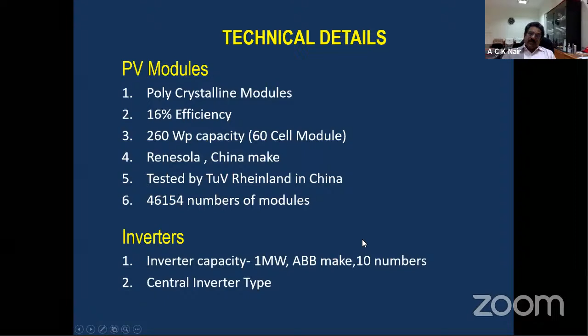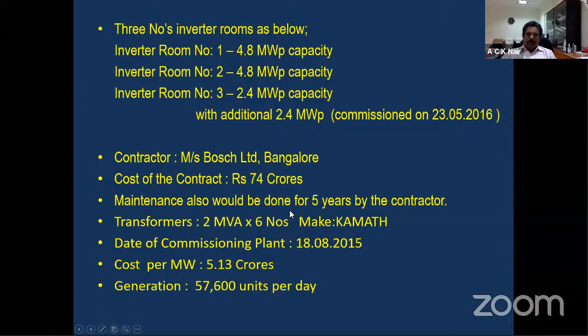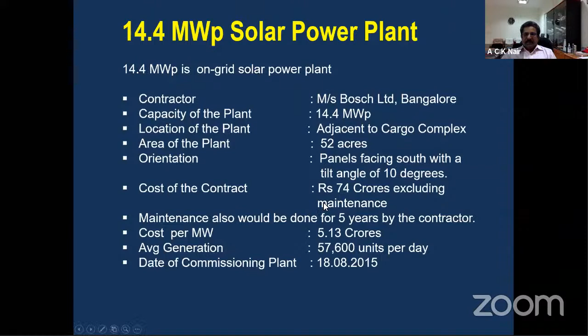We have 3 inverter rooms for the 12 megawatt plant: inverter room 1 with 4.8 megawatt capacity, inverter room 2 with 4.8 megawatt capacity, and inverter room 3 with 2.4 megawatt capacity, with an additional 2.4 megawatt added in 2016. The contractor was Bosch, and the contract cost was around 74 crores, with maintenance included for 5 years. We have 6 transformers of 2 MVA each. Date of commissioning was 18/8/2015, and cost per megawatt was only 5.13 crores. So these are some of the details, and this was later upgraded to 14.4 megawatt.